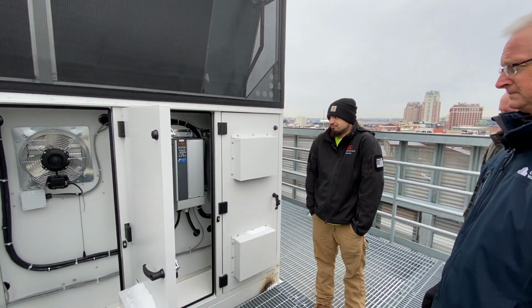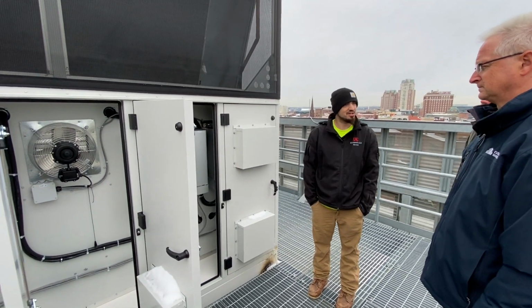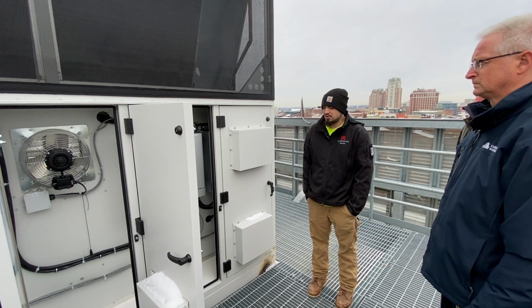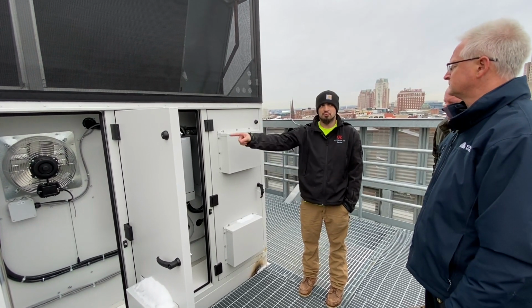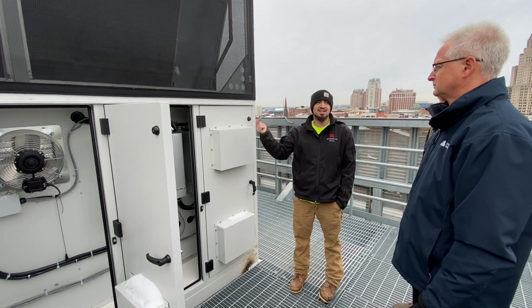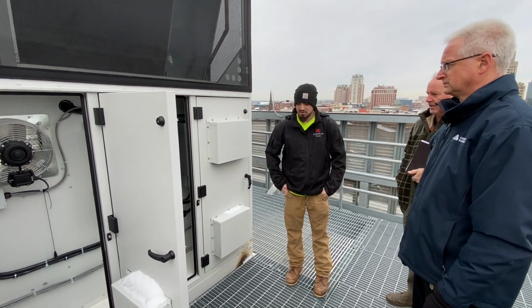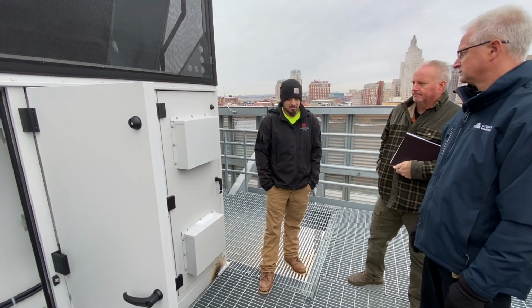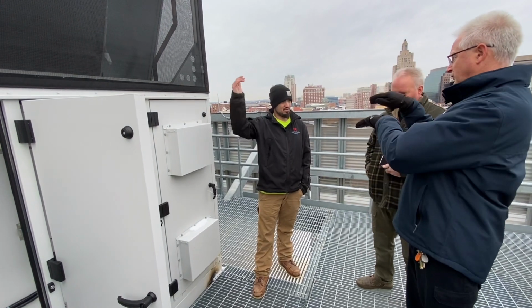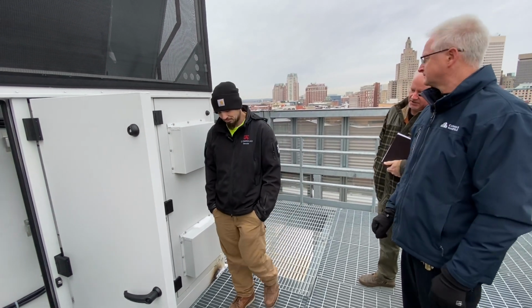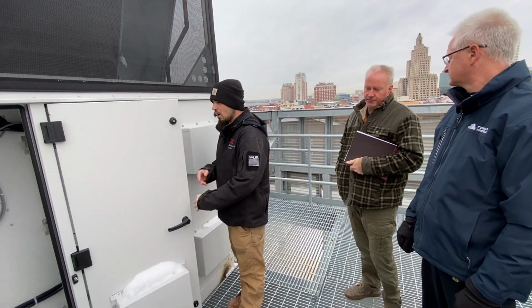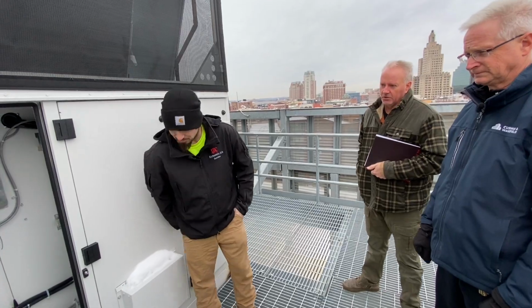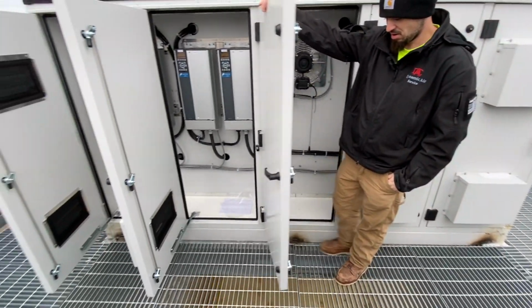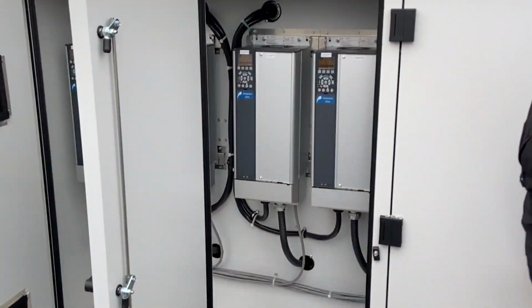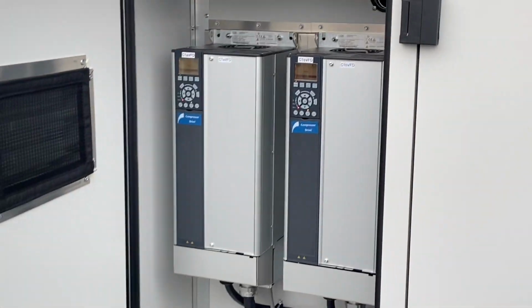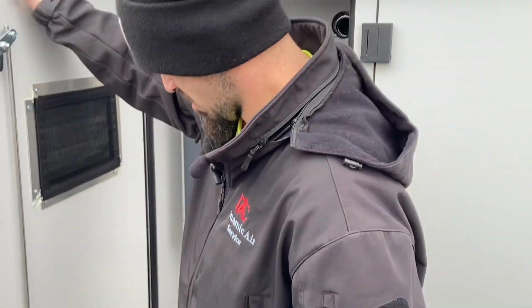Same thing as any other VFD, pretty much. I believe it's one stage to 50%, and then it brings the next stage on, and that's how it modulates. Right. So you actually have 8 modulating stages total. So instead of running 1 to 100, running 3, 4, 5, 6. Okay. And I think Annex Air does a lead lag where they'll switch off the first circuit on hours, so you'll try to do equal balancing so one stage doesn't get all the runtime. Yep. Because in this part of the country, there's a lot of that. Exactly. Then the ECM fans should modulate based on head pressure, so they'll speed up as they need to.